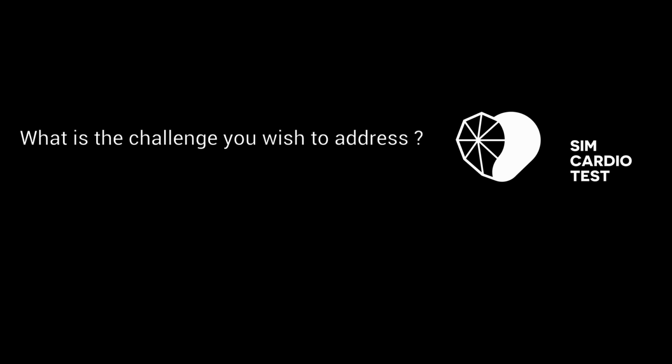So we have two types of challenges. The lead has to be inserted into the blood vessels. It navigates from an entry point on the skin down to the heart cavity, in which the lead itself has to be attached to the muscle. So the one question concerns how this small cable, the lead, can navigate into the complex tree of vessels down to the heart. The battery delivers an electrical impulse through the cables to the electrodes that are in the heart.